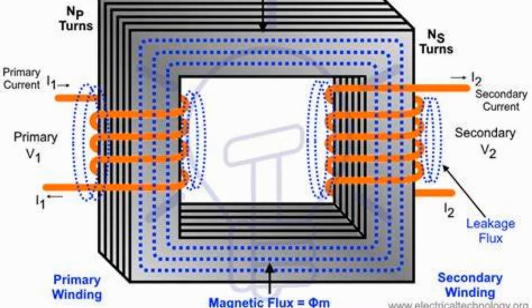When you apply the voltage on the primary winding, the flux gets induced proportionate to the primary voltage, and that flux links with the secondary winding through a magnetic core, which is called mutual induction. That linked flux induces a voltage in the secondary winding proportionate to the number of turns. If the number of turns is more compared to the primary winding, the voltage gets increased, which is called a step up transformer. And if the number of turns is less compared to the primary winding, the voltage will get reduced, so it is called a step down transformer.